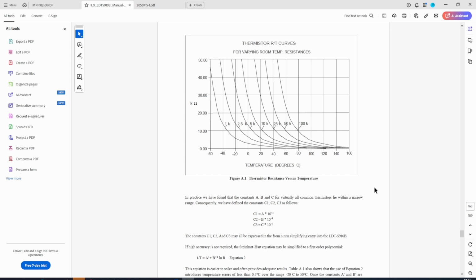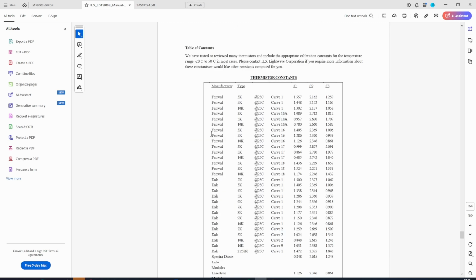So in order to do that, you've got to take lots of very precise temperature readings and then solve a lot of maths in order to work out the 3 coefficients for your device. ILX actually provide some of the coefficients for certain makes. It tells you some values that you can use for the coefficients, and you'll see there's quite a lot of variety in these coefficients, even in the same manufacturer for their different types of thermistor.